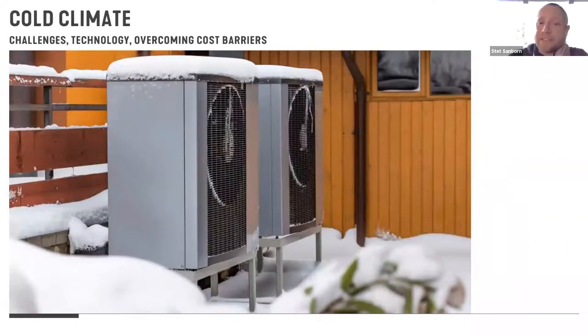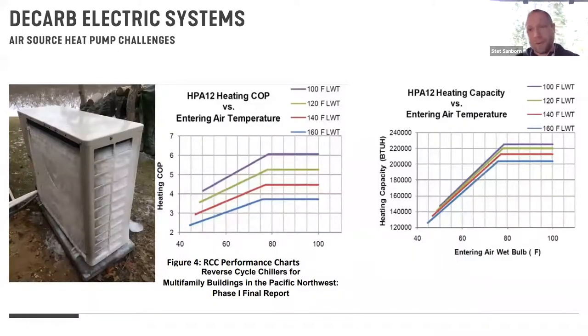So one of the big challenges when we translate some of these ideas into cold climates, and I hear this a lot, is this. Over the last year and a half, I've been on the ASHRAE committee that's been writing the new multifamily zero energy design guide. And as we are going through all the system recommendations for that, we're still putting system recommendations in all the way to ASHRAE Climate Zone 7. And so we had to make sure that there was feasibility around that. A lot of the info I'm sharing is coming out of the research that Dan Nall, who's in New York City, and I were doing to look at how this technology translates to cold climates.